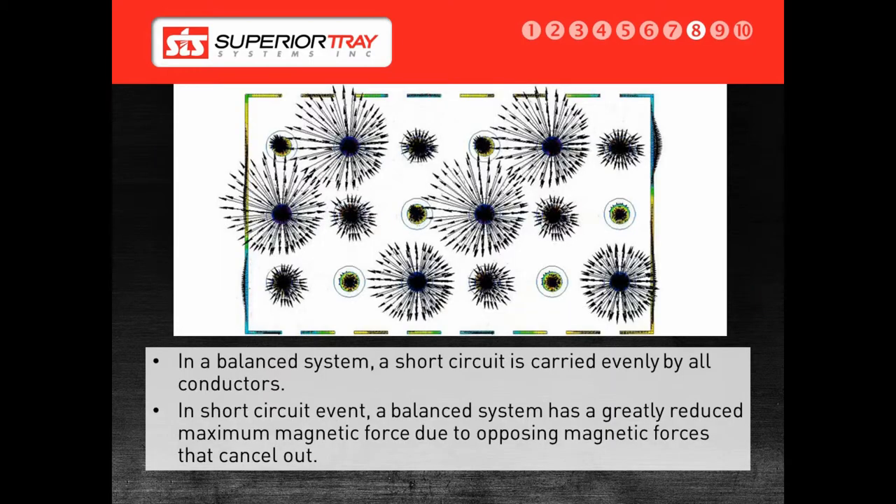One of the major differences between cable bus and any other wiring method is the short circuit rating. In a balanced system, the conductors are arranged according to phase within a Superior Bus. The arrows shown on the presentation slide are the magnetic forces from the cables as power is transferred through them at a 50 or 60 hertz frequency. In the event of a 100 kilo amp, or KA, short circuit, 100,000 amps are going to run through the conductor on the phase that has a fault. On a bus bar, a single conductor takes the full 100 KA load, resulting in massive forces generated between the bus bars.